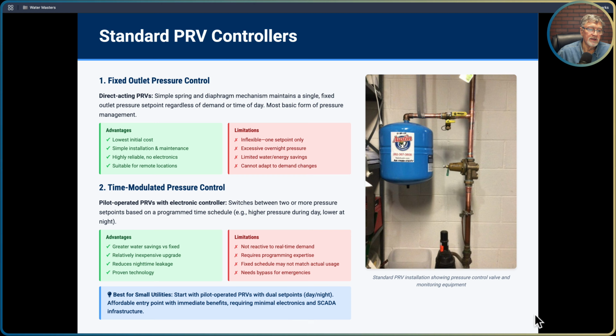So now we go into the time modulated pressure control. This is a step up because it's a pilot operated PRV with an electronic controller, and it's going to switch between two or more pressure set points based on a programmed time schedule.